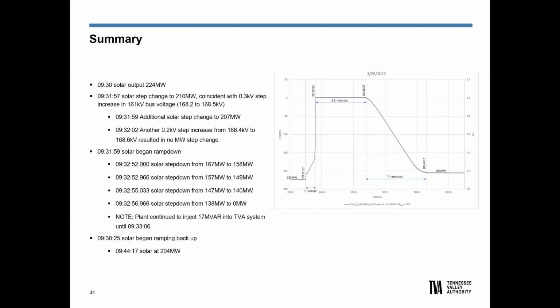There was nothing going on in the power system. There was nothing going on at the plant that we were aware of. We contacted the plant controller, the plant operator. They were also not aware of anything going on. What happened here was actually a communication dropout. They had a firmware device that was patched that dropped their communication out, and they dropped to zero because comms dropped out. So it's all these different things that we're seeing after commissioning, after our 14-day period, that we're seeing issues with. And again, we've seen lots of issues. If you just compare that to how little we have installed already, that's our concern.